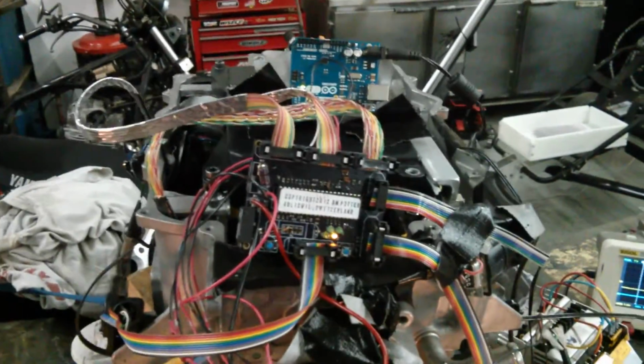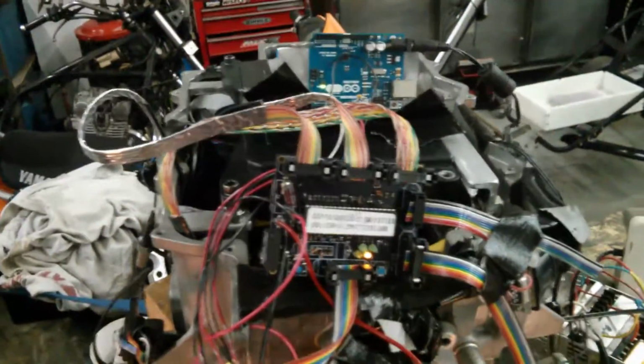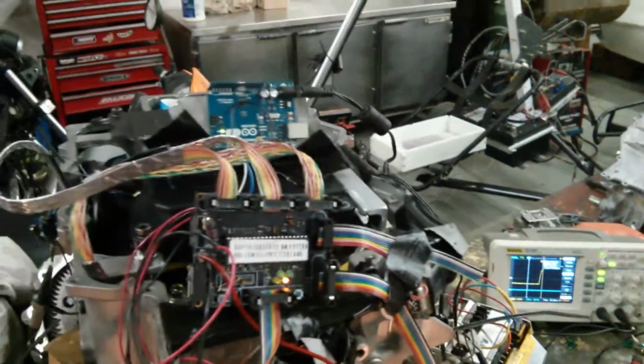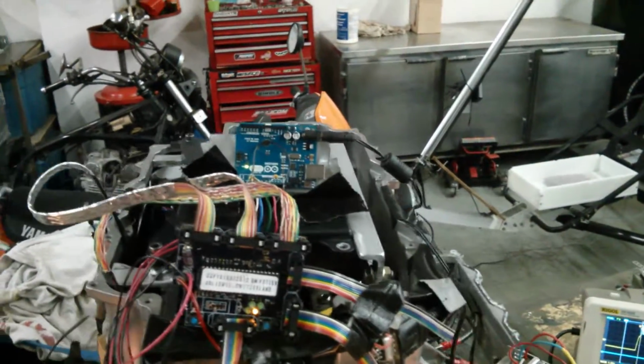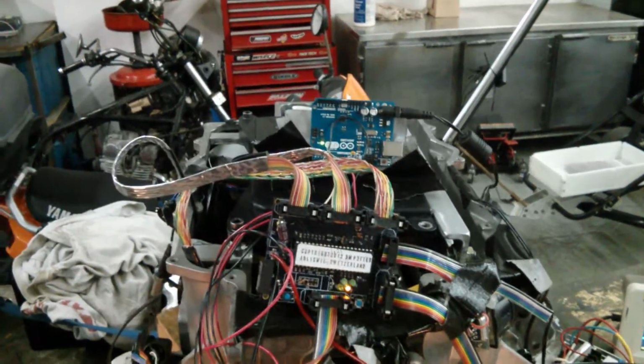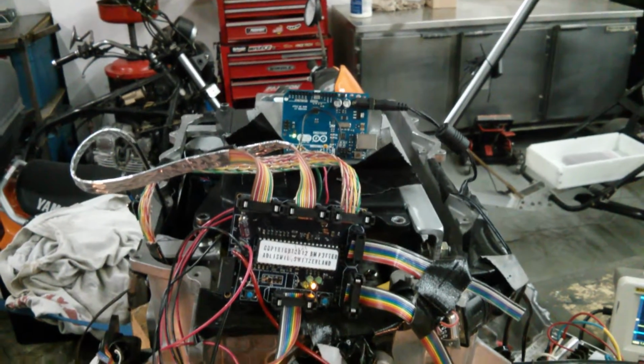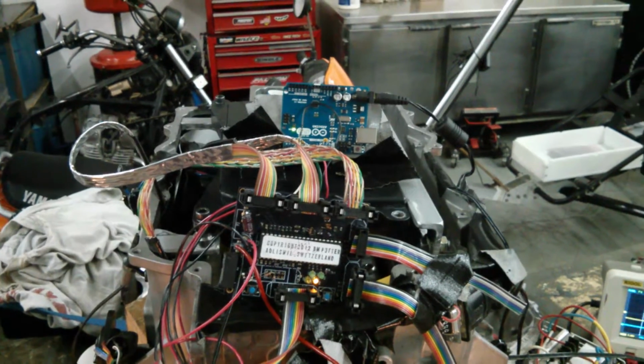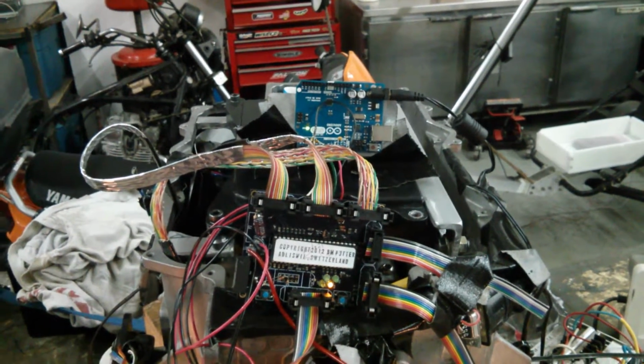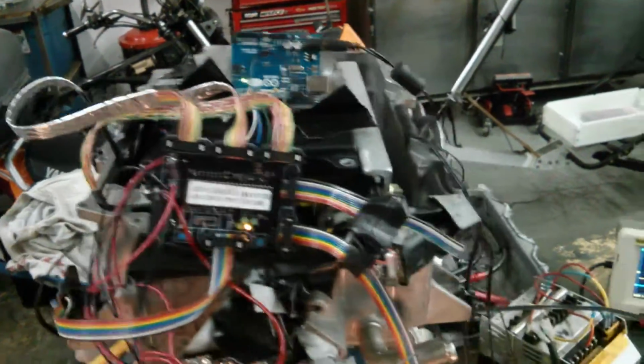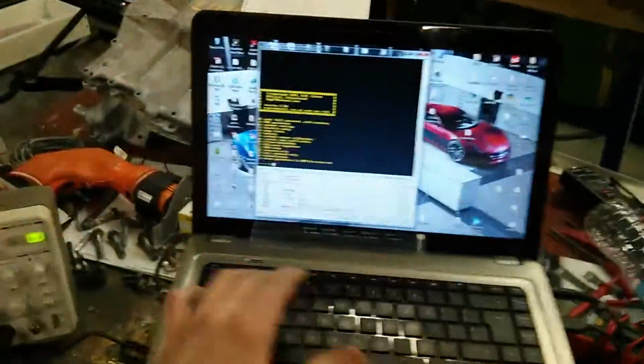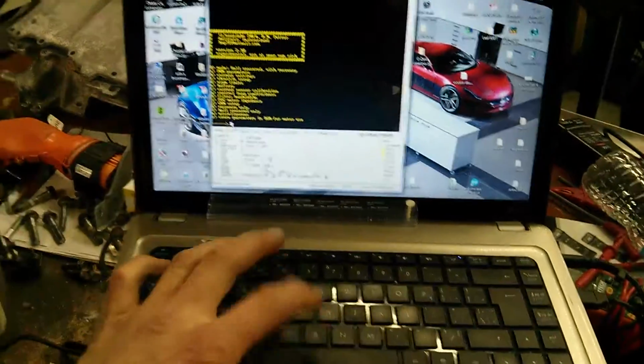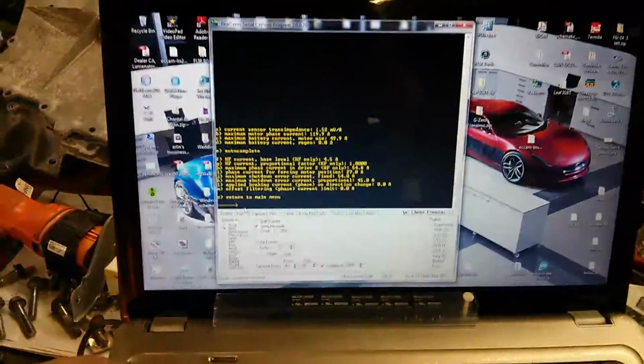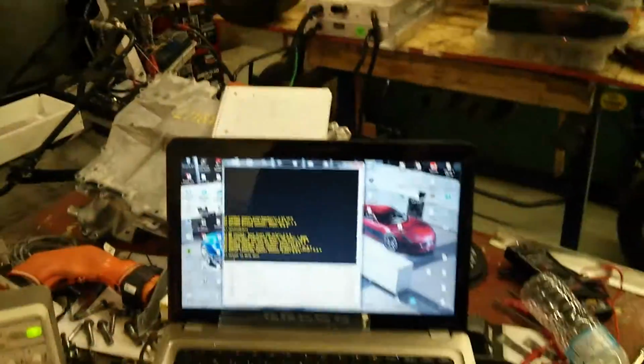Just earlier I loaded a backup calibration file I had saved, and for some reason it saved incorrectly, and it set my current sensors at 280 millivolts per amp, which is insanely high considering my current sensors are about 2.53 millivolts per amp, I believe. I'll just go into the settings menu here and check it, current settings B: 1.52 millivolts per amp. So it was actually 200 and something millivolts per amp.